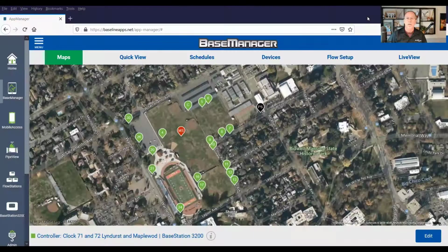To do that, let's jump into Base Manager. I've already logged into Base Manager with my username and password, and I'm on the maps page. The thing I'm looking for is in the lower left corner where it says controller clock 71 and clock 72. That's green. The controller is idle. Green means go, or it's ready to go. If it was gray, the controller would be offline, and it could be for a couple of reasons. It could be that the controller doesn't have a good communication method, that the cell modem is down or Wi-Fi or whatever your networking connection is down, or it could be that the controller is not powered up and it's not actively working. So that wasn't the issue with this one.